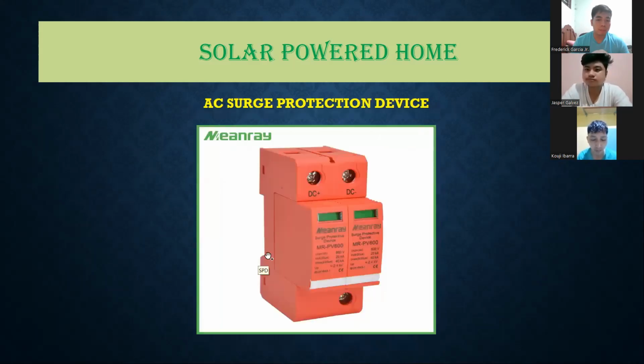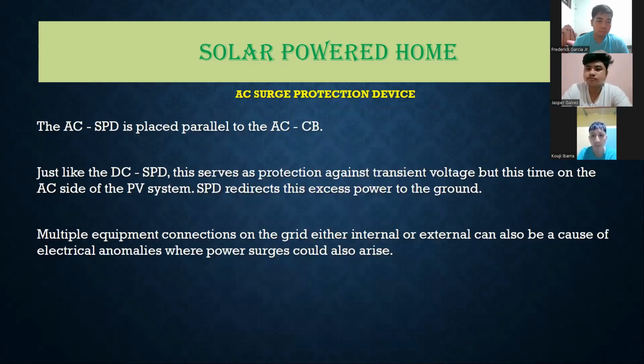We have another example, of course. You can see transient current rather, of 20 kiloamps, at 20 microseconds. And it's rated for 600 volts. Okay, good. Now we have the AC surge protection device.